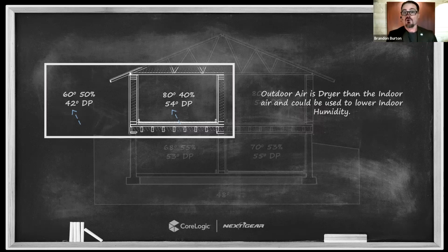the more energy is required to suspend that moisture. So it is drier outside than it is inside. It's automatic. If you open up a door, you open up a window, or give any other means for a transfer or movement of moisture, the moisture will move from inside to outside. It could be 100% humidity outside, and that would still happen, okay, as long as the dew point is lower outside. So that's the first thing that I know, and I know it for a fact.